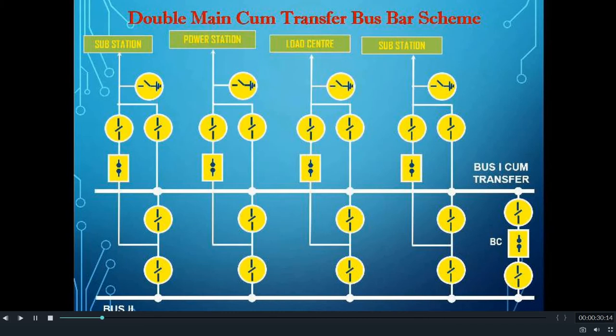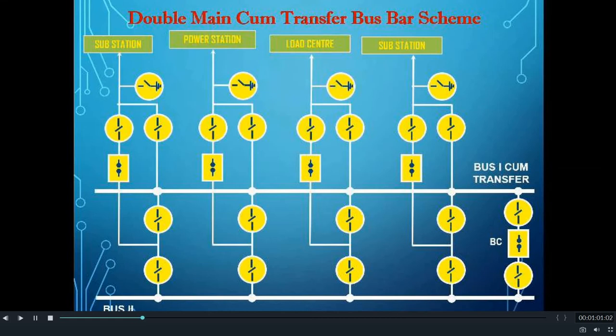Before I explain how this double main and transfer bus bar scheme works, let us see how this double main come transfer bus bar scheme is different from the double main bus bar scheme. In this type of bus bar scheme, the number of isolators used per feeder is 4. Two isolators are used to connect the feeder to either of the buses, one isolator is used as a line isolator, and another isolator — the extra one from the double main bus bar scheme — is used as a transfer isolator.